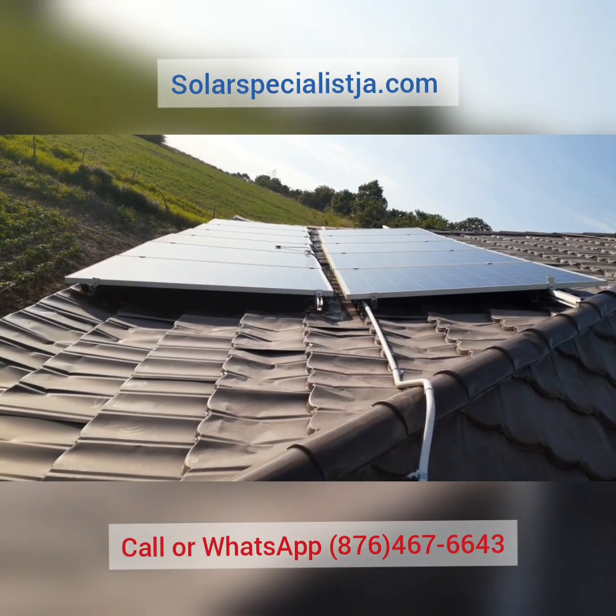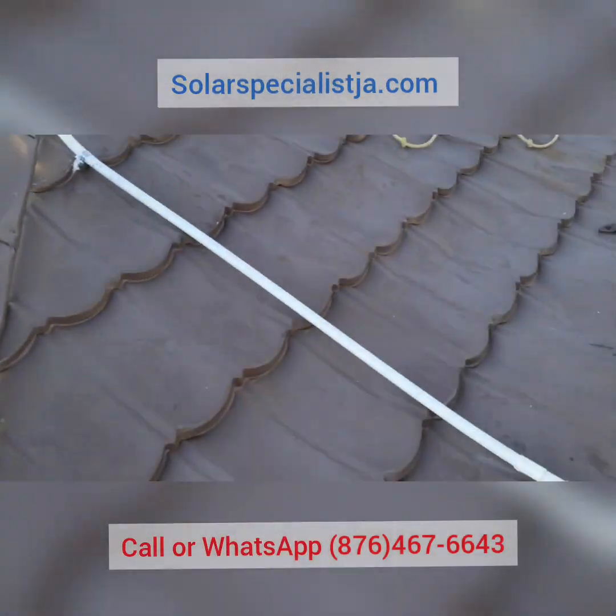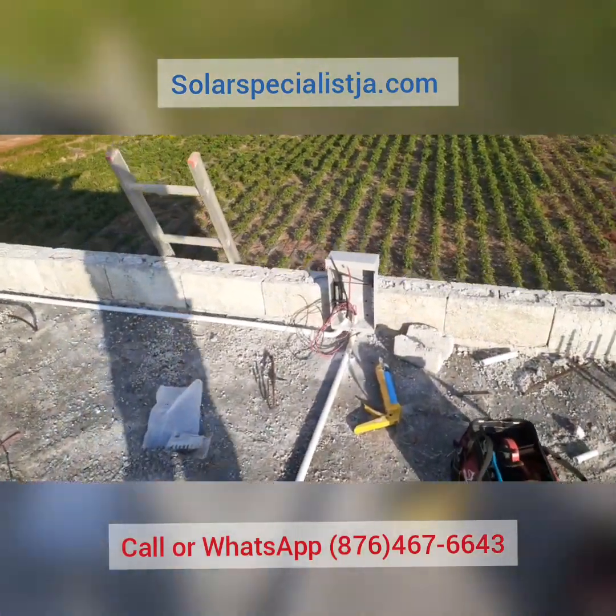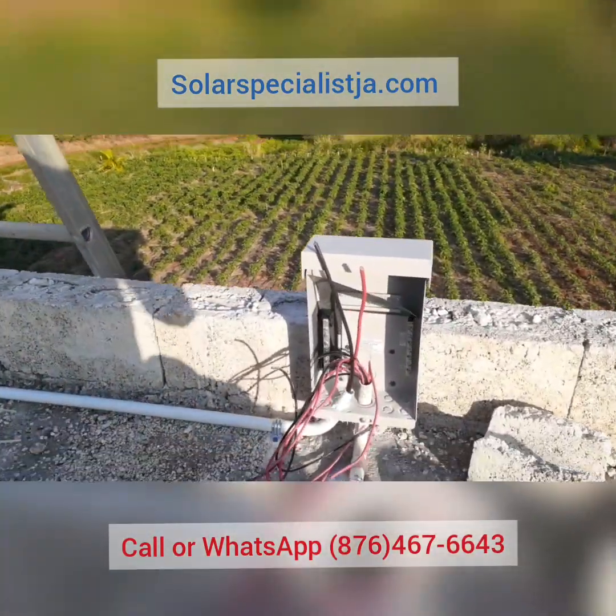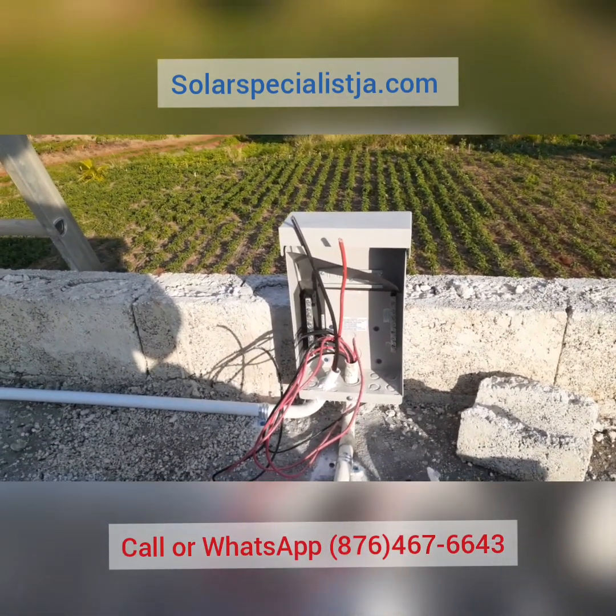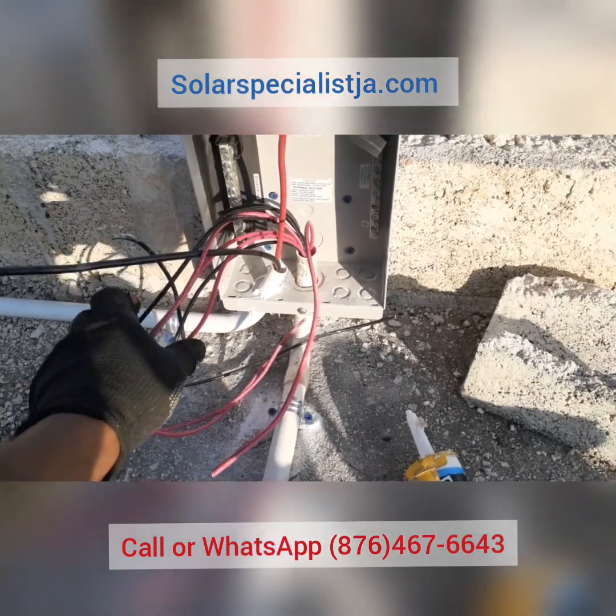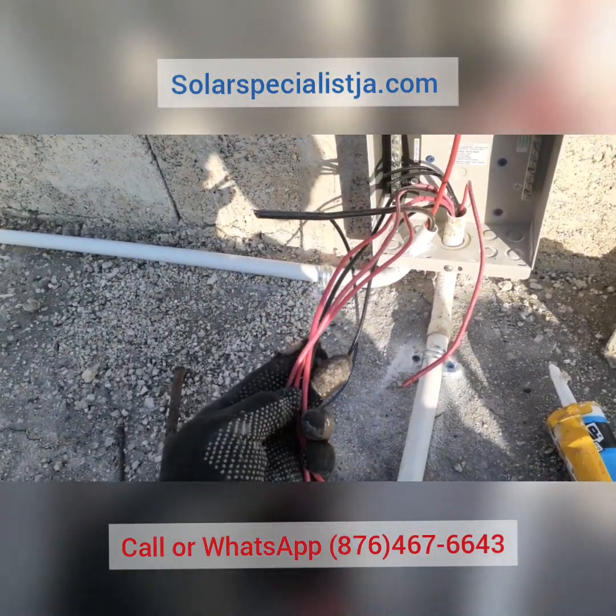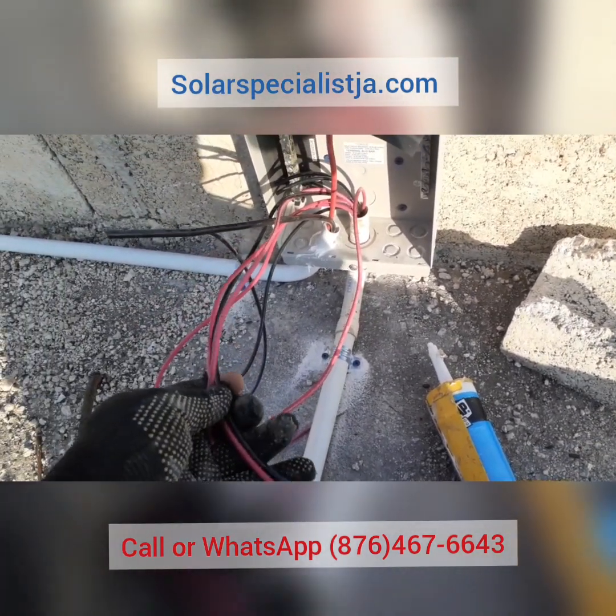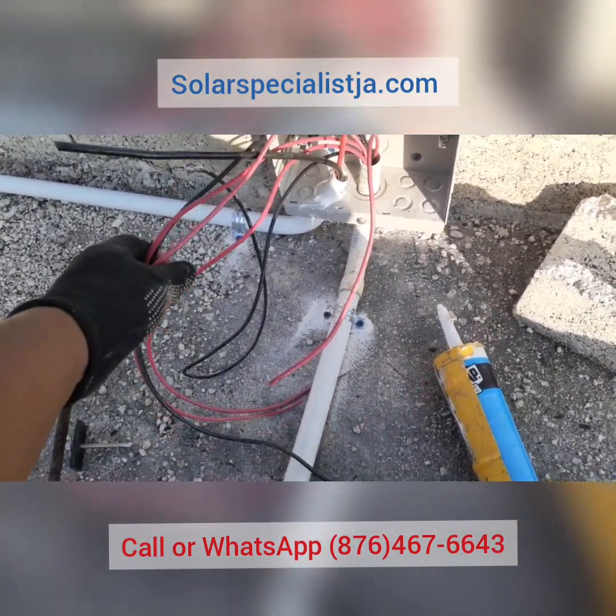We're in the process of getting this thing rectified. As you can see, we run our main line and this line was not protected, so we went ahead and installed a six-way DC panel combiner box from MidNite Solar. In our combiner box, these smaller wires are designated to each string — these smaller wires are 10 AWG DC wires, so we have four reds and four blacks.